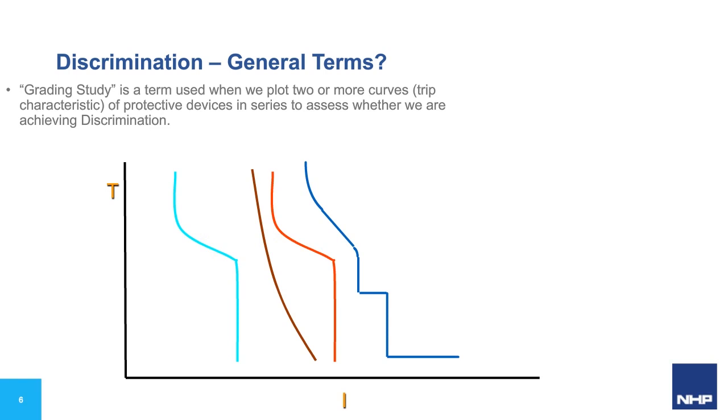This means that lower current levels take a longer time to trip the protection device, hence the term long time trip or setting. This is provided by thermal protection on thermal magnetic breakers or long time setting on electronic breakers, IN nominal rating or IR as adjusted trip rating.